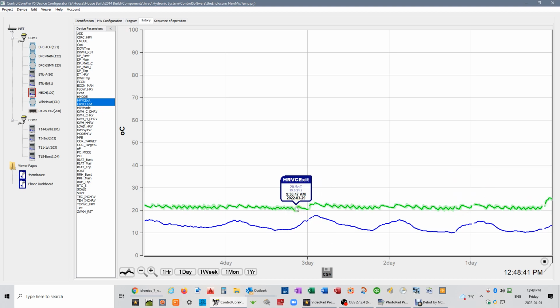This is getting untempered water from the buffer tank. So this does not go through the mixing valve, which is why you are seeing these frequencies. This is matching the buffer tank's high-low allowable temperatures based on the heat pump being on and off. But you can see with just a little bit of hot water going to this coil, we've been able to pretty much consistently have the incoming air at room temperature. So what that means is that the supply ports that this air is coming out of into certain rooms, that air is at room temperature and it's not chilly. It's not creating a cold inflow of air.